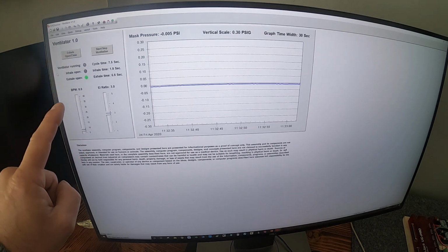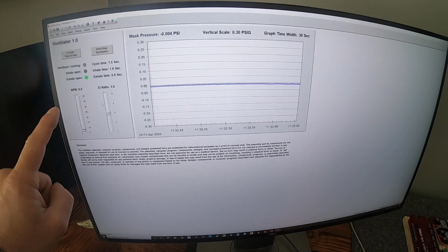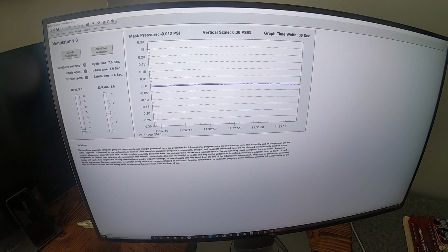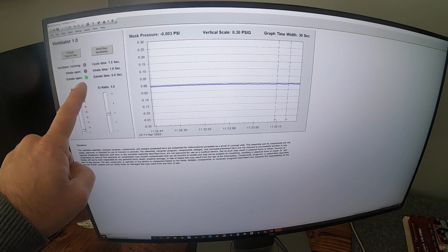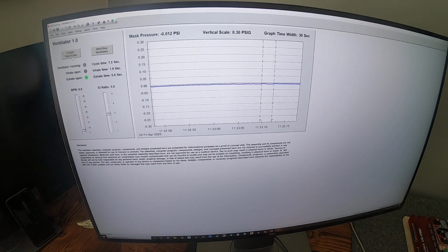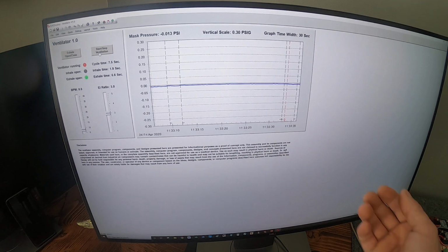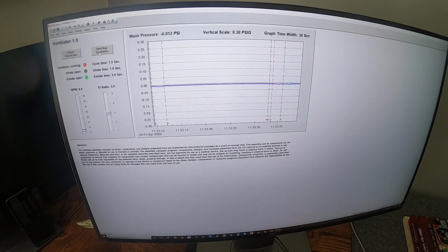A button here in the upper left will open and close the exhale valve. When it's open, you can see this virtual LED becomes green to show that it's open. This is useful for putting the mask onto someone because they can breathe freely through the exhale tube while this valve's open. The other button initiates the automated ventilation cycle. I'll press that, and you can see a ventilation cycle begins. Now you don't see any pressure displaying on the graph because I don't have the mask hooked up to someone. It's just venting into the atmosphere, so there's no pressure buildup.